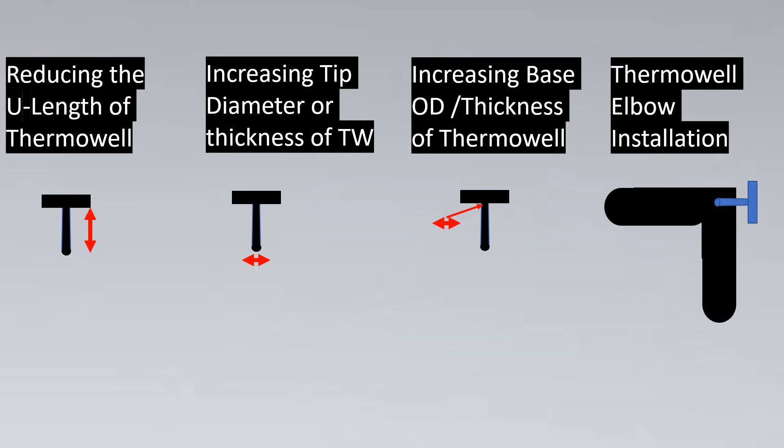If you imagine this is an elbow and we insert a thermowell here, the tip as per ASME PTC 19.3 should be facing towards the flow, that is the recommended installation practice. So here's the flow, and what happens is majority of the velocity is hitting the tip, so the probability for von Kármán vortices to be formed reduces greatly. This is another way you can use if your wake frequency calculation is failing for your thermowell.